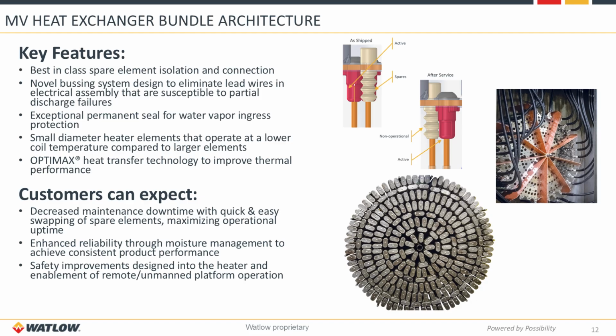Watlow also uses a small diameter heating element which operates at a lower coil temperature compared to larger elements. This helps extend the life of the system and improves efficiency. OptiMax heat transfer technology improves thermal performance and reduces the pressure drop across the heater. Some of the benefits that customers can expect are reduced maintenance downtime and thus maximized operational uptime, enhanced reliability through moisture management mitigation during manufacturing to achieve consistent product performance, and finally, safety improvements that enable remote and unmanned operations.